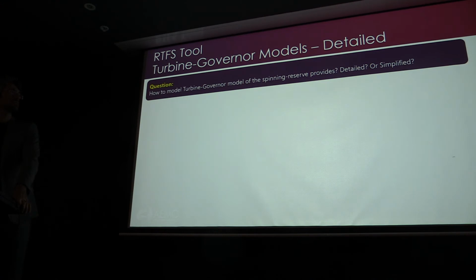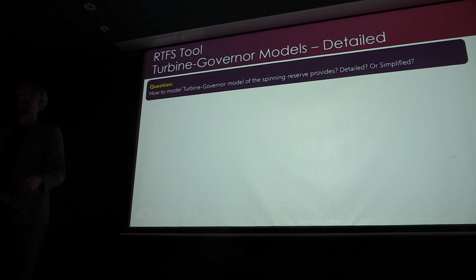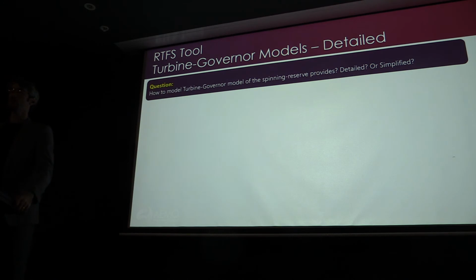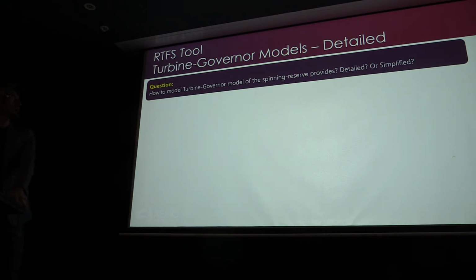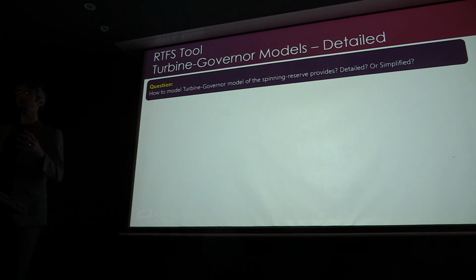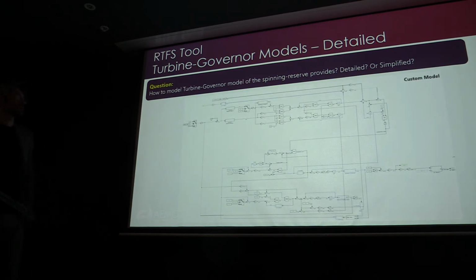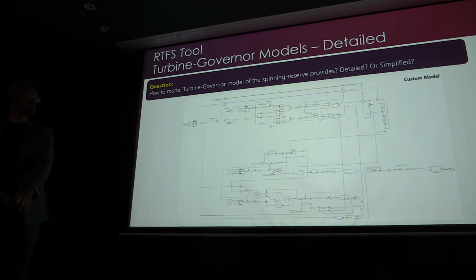Now, the next important part of the model is the droop model. As I said, we consider the turbine governor model of each machine separately, and we calibrated each separately based on actual measurements from past events. So how do we model the turbine governor model of the spinning reserve providers? We had to decide whether to use a detailed model or a simplified model. This is just an example of a detailed model, a custom model for one of the generators. You can see it's very complicated, and in terms of computational burden it would be very hard to use in real time.